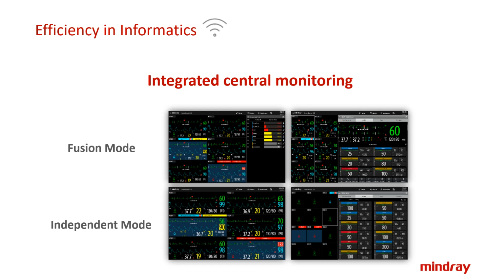There are two modes: fusion mode and independent mode. In fusion mode, it combines with the patient monitors, so after clicking split windows on the central station you can see the patient monitor and infusion pump display in one window. In independent mode, it's not related to the patient monitors. If you click the icon of the infusion pump, you can see it on the screen, as shown in the picture here.